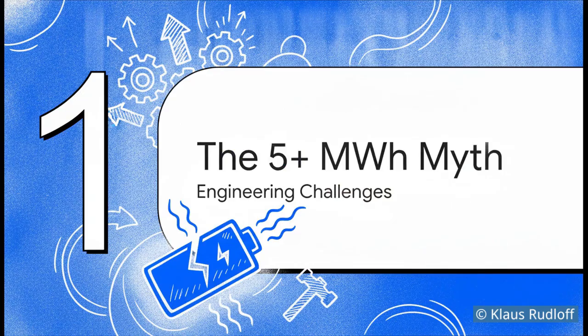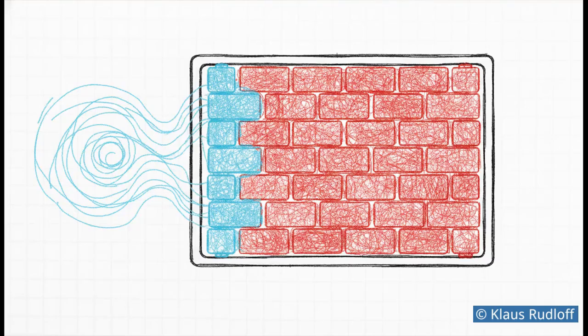Moving to Section 1, the 5+ megawatt-hour battery myth. Let's look at the primary engineering challenges making this myth unravel. When we're dealing with these massive densities and oversized enclosures, maintaining uniform airflow and cooling across every single module becomes practically impossible. You simply can't push air evenly over thousands of tightly packed cells. It's exactly like trying to air condition a packed stadium from a single vent at one end. The people in the front are freezing, but the folks in the middle are sweltering.